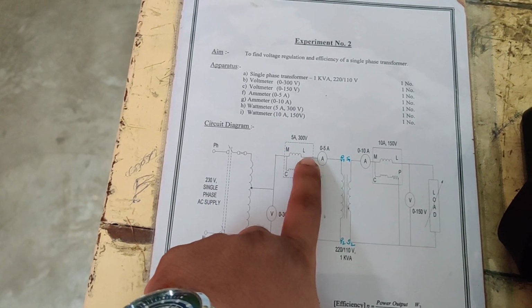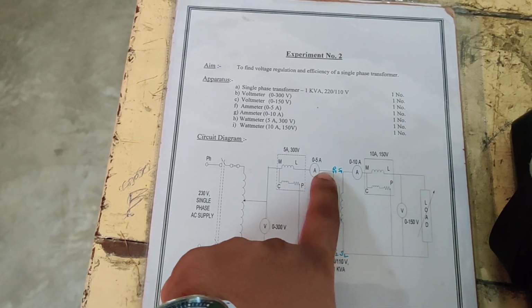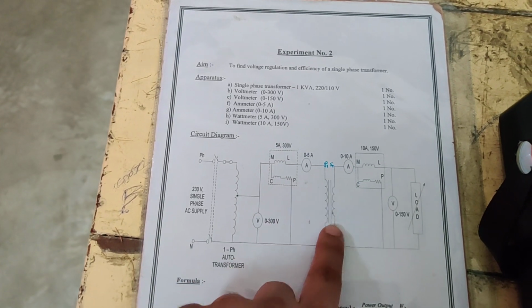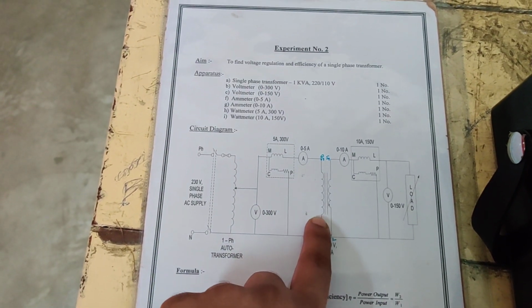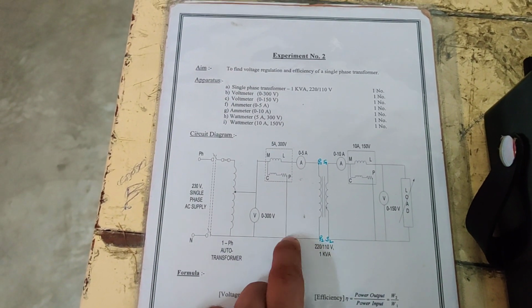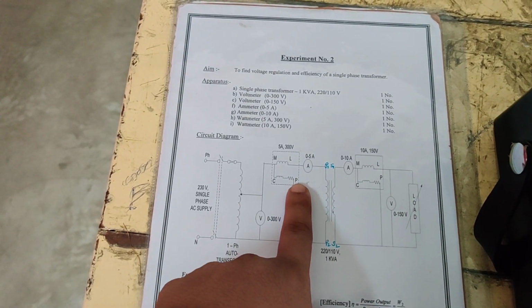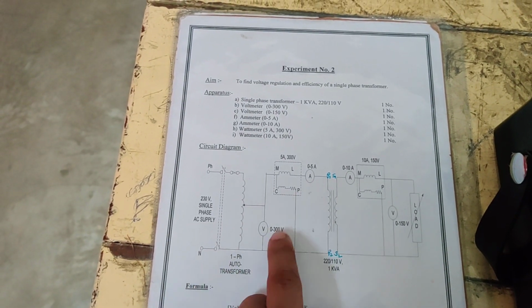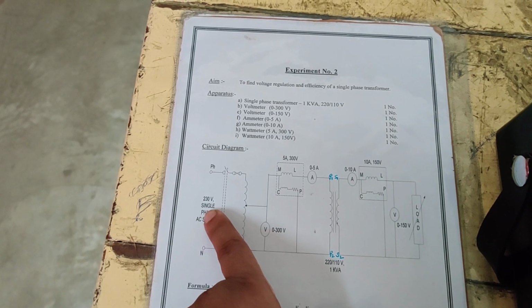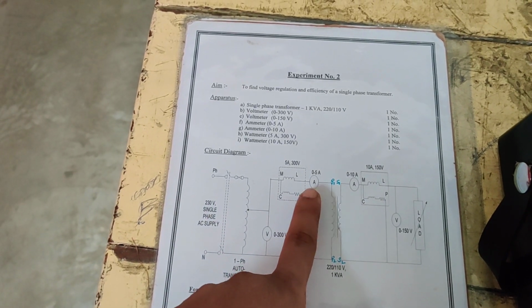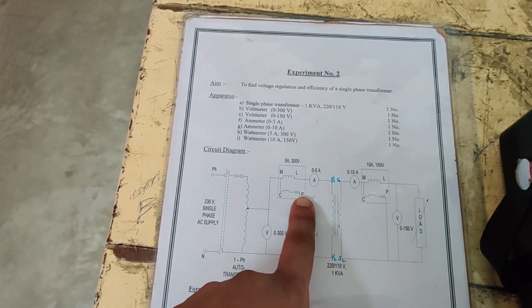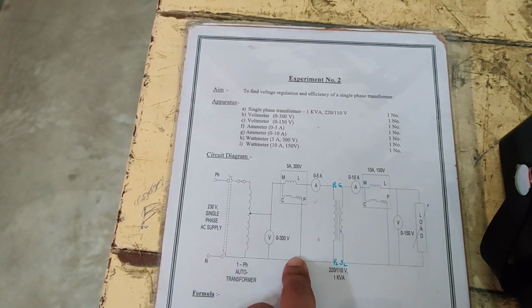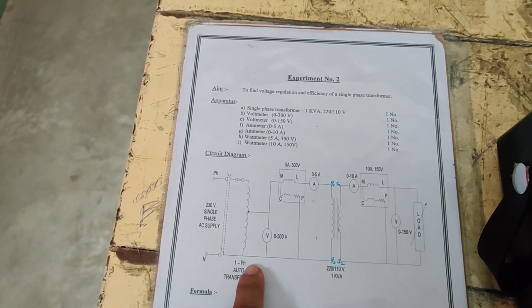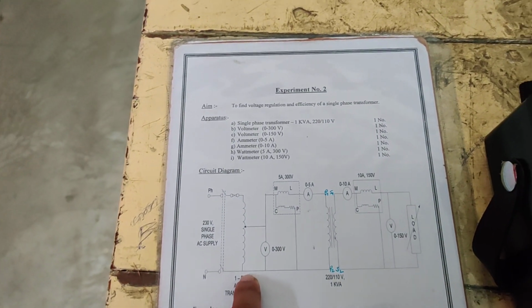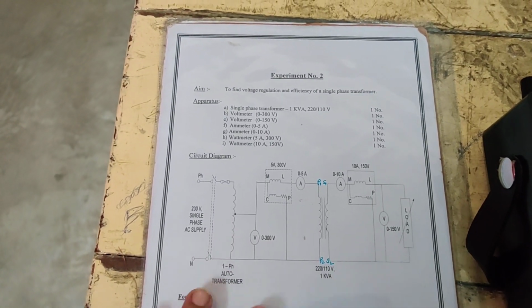This is known as the current coil. From L it is connected to the ammeter, from the ammeter to P1, which is the primary side of your transformer. From P2 it is connected to the voltage range, that is 300 volts, because we have to measure 230 volts. We have used the common terminal here, and from here it is connected to the auto transformer's neutral terminal. So this is the connection of the primary side.